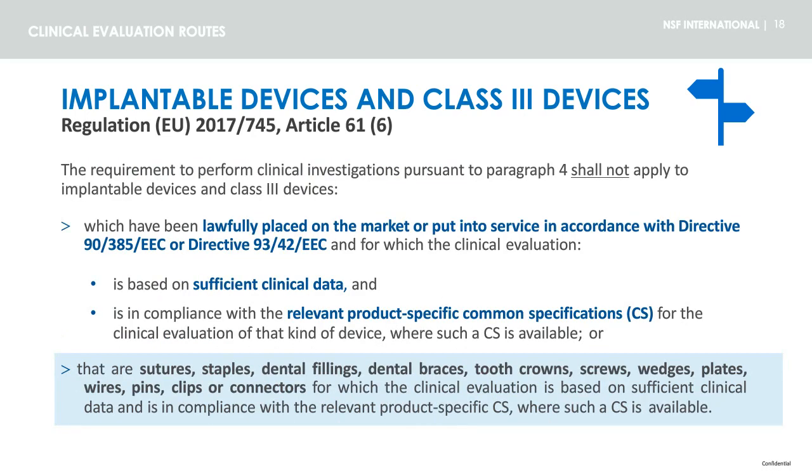In paragraph 6, it's also stated that the requirement to perform clinical investigation does not apply to implantable devices and class 3 devices which have been lawfully placed on the market or put into service in accordance with the directives, as well as if they belong to product types such as sutures, staples, dental fillings, dental braces, tooth crowns, screws, wedges, plates, wires, pins, clips, or connectors.